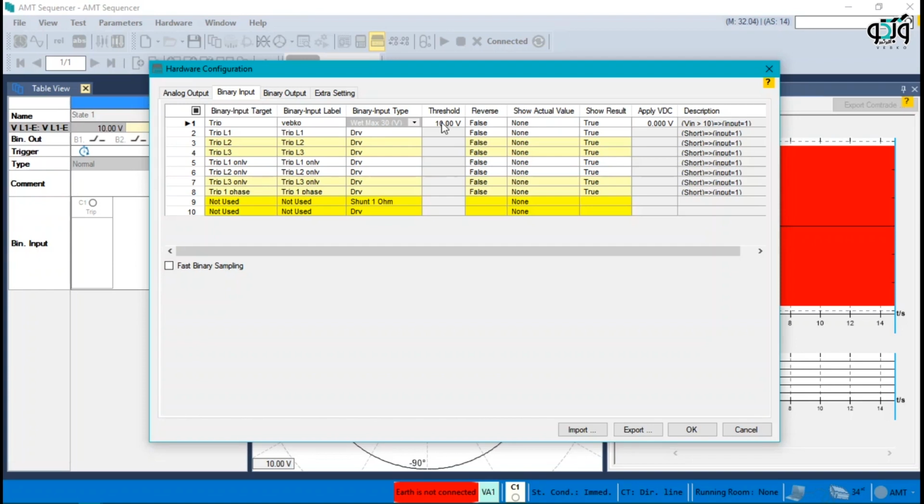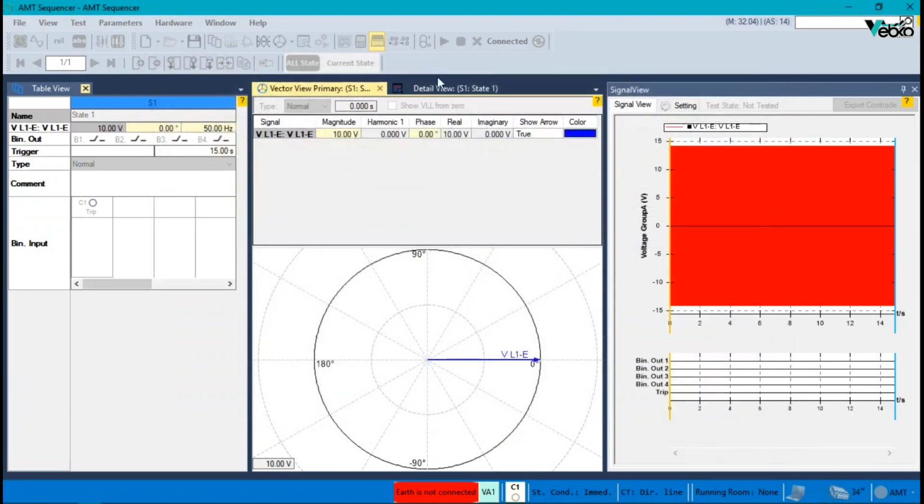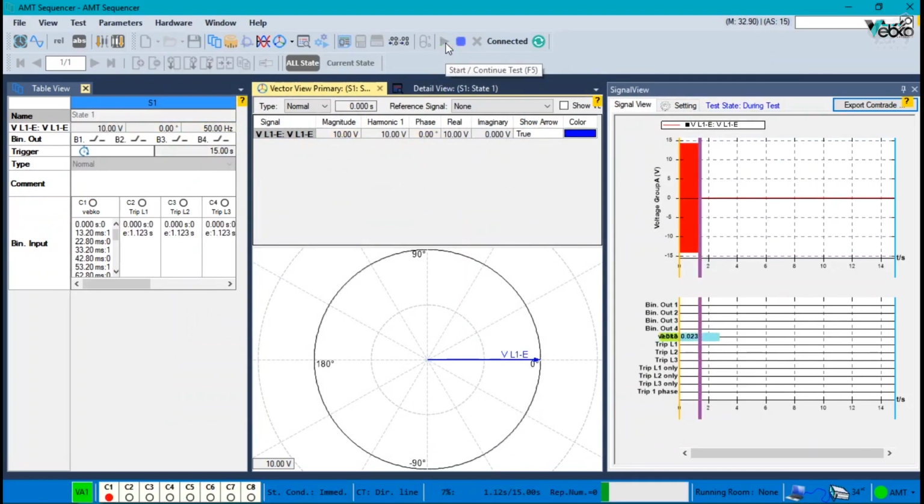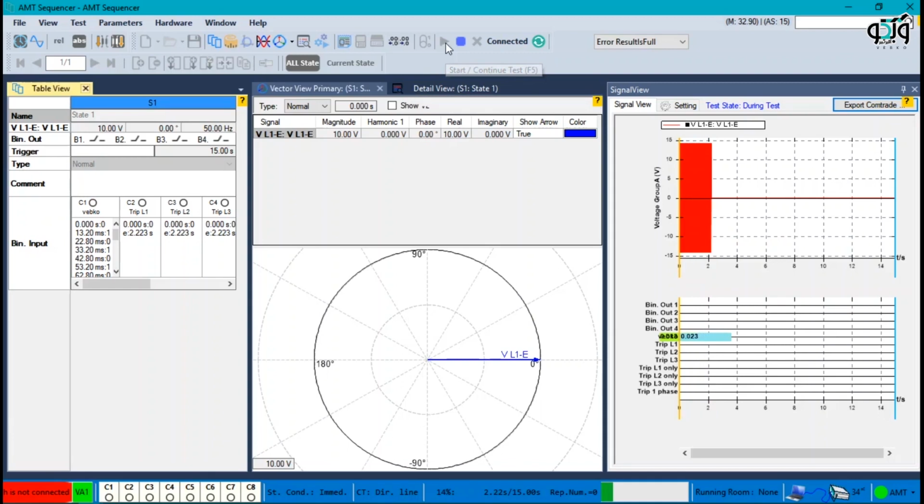If the binary input is used for measuring the voltage, it is important to select the maximum level of wet measurement. For example, to measure 23 voltage, the wet maximum 30 voltage must be selected. If wet maximum 4.5 voltage is selected, when the voltage exceeds 4.5 voltage, the software gives an overvoltage binary error message.